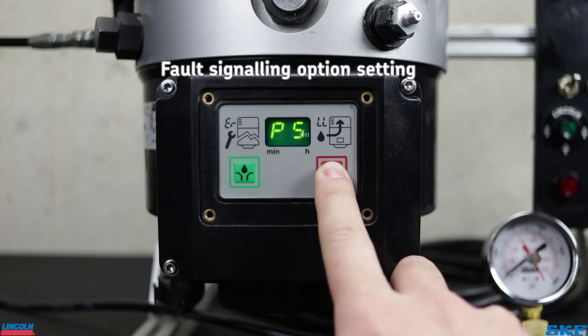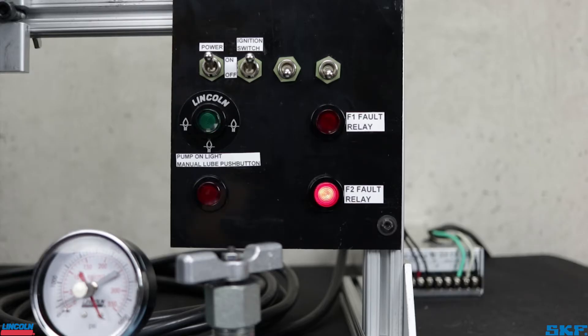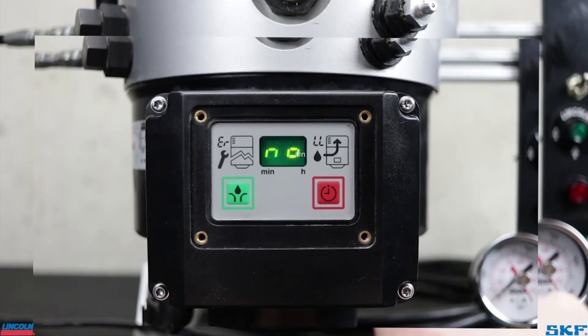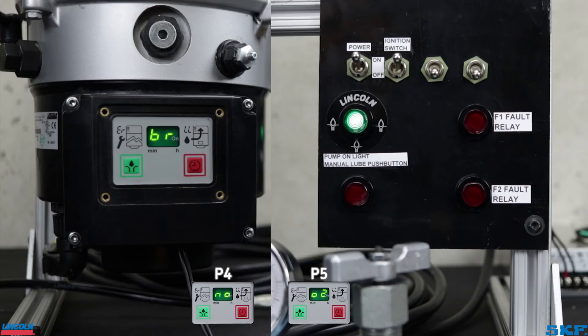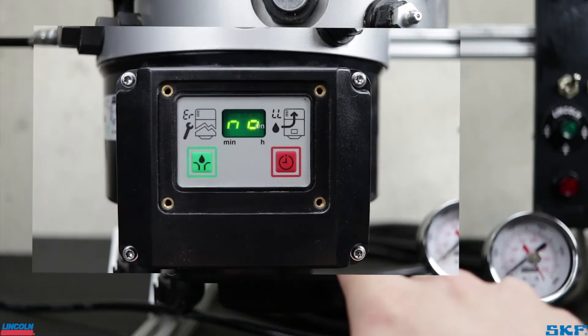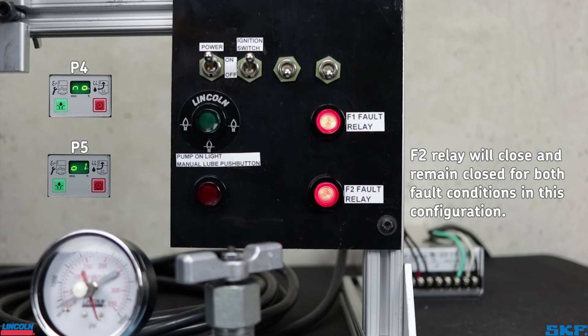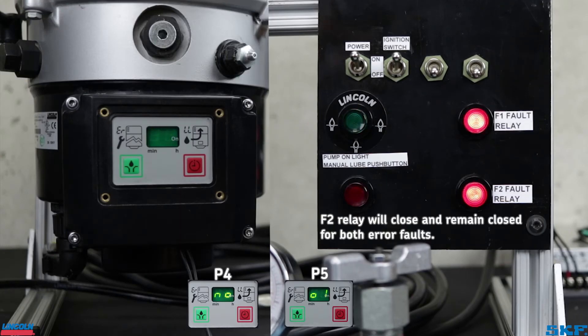P5 is the fault signaling condition. Factory setting is O2, or option 2, as shown here. This means the different fault signals are separated between the two fault relays. For example, with P4 set to normally open and P5 set to O2, if you receive a low level code on the unit, it will close the F1 relay contact on the board and illuminate the corresponding light. Should a pressure error fault occur, the F2 relay contact will close and illuminate the corresponding light to signal a pressure fault. Now leaving P4 at normally open, but setting fault signaling to O1, or option 1, this sets the F2 relay contact up to receive both faults in the form of codes. If a low level trips, the relay will repeatedly open and close, flashing a light on the panel. If a pressure error occurs, the F2 relay will close and remain closed, or turn on the light.